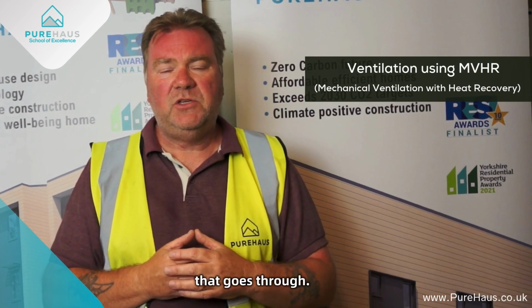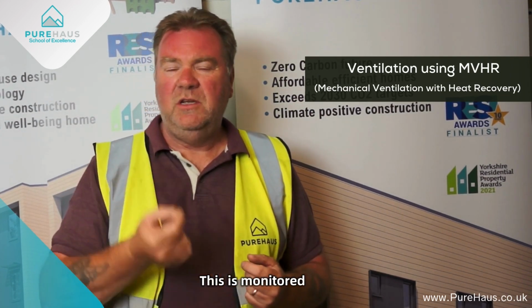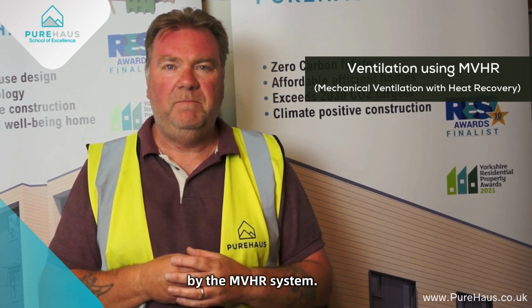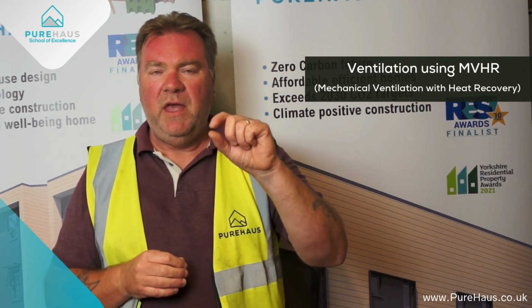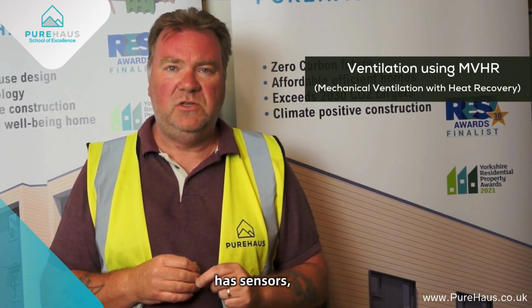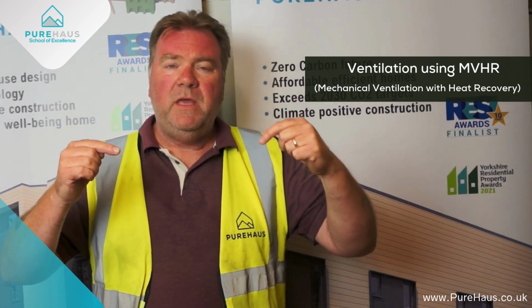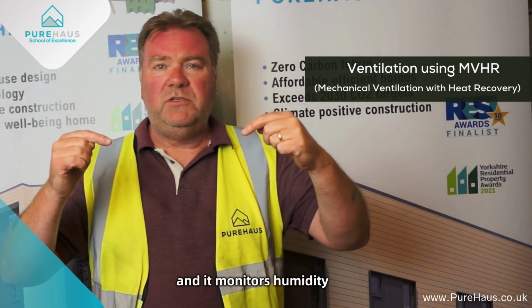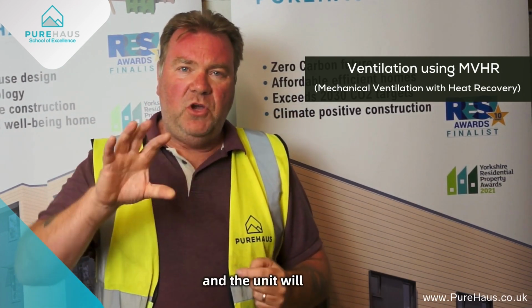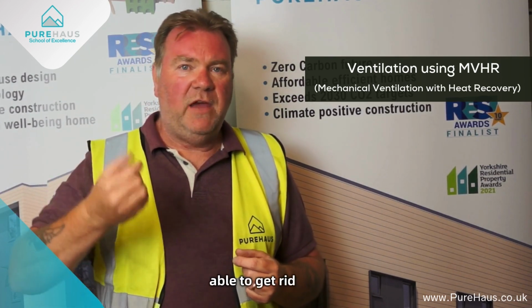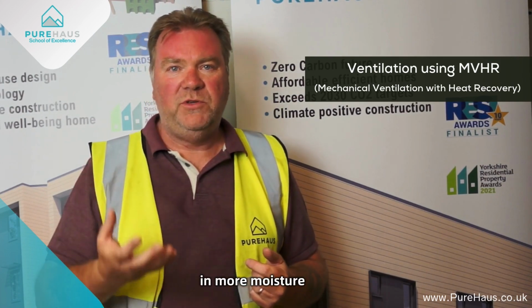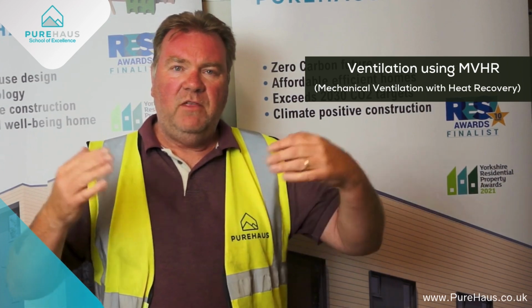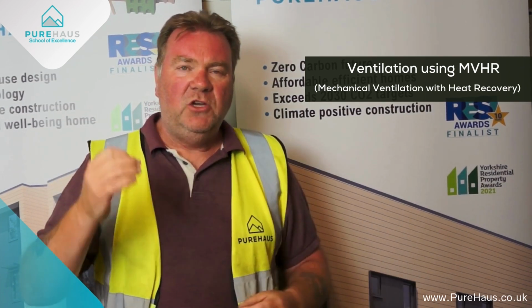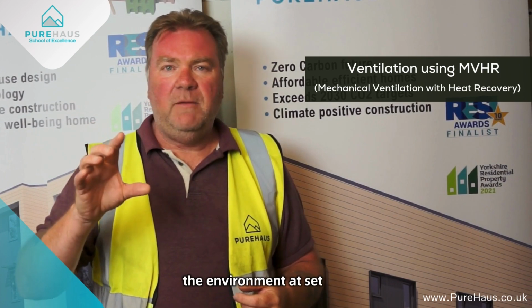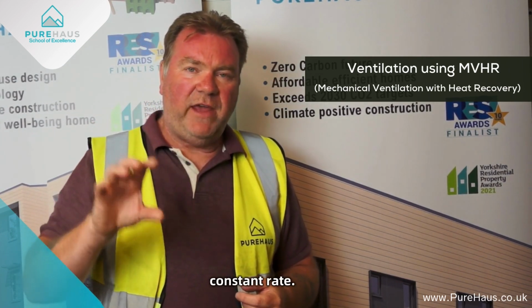This is monitored by the MVHR system. Every MVHR system has a monitoring system, has sensors. It monitors airflow, it monitors temperature, and it monitors humidity. And the unit will adjust itself to get rid of more humidity and more moisture if you need it. The fans will change automatically to try and keep the environment at a set constant rate.